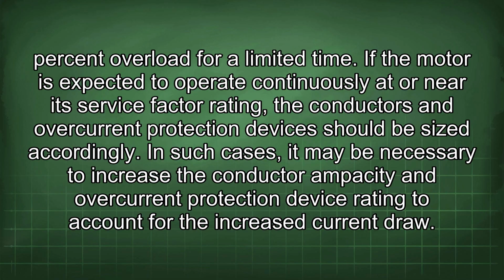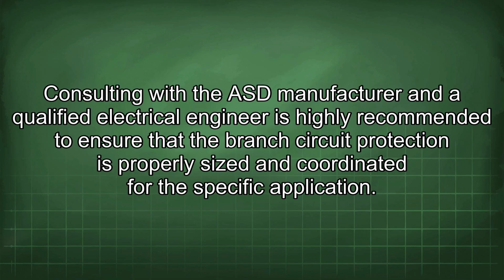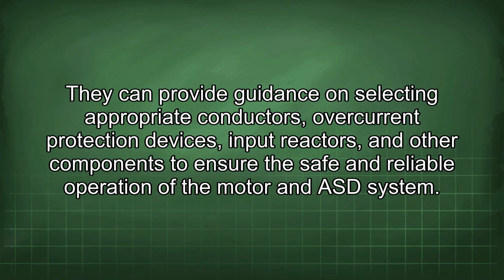the increased current draw. Consulting with the ASD manufacturer and a qualified electrical engineer is highly recommended to ensure that the branch circuit protection is properly sized and coordinated for the specific application. They can provide guidance on selecting appropriate conductors, overcurrent protection devices, input reactors, and other components to ensure the safe and reliable operation of the motor and ASD system.